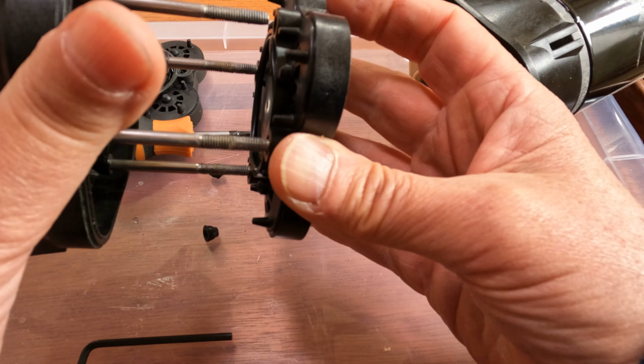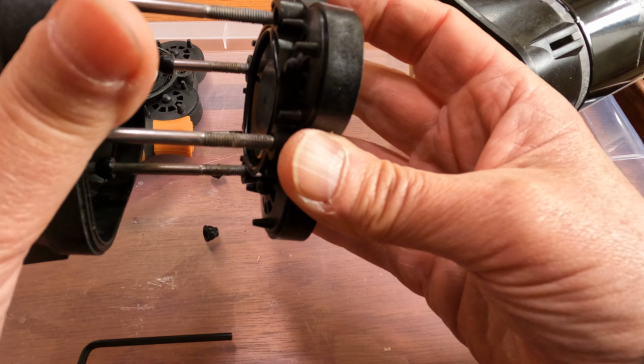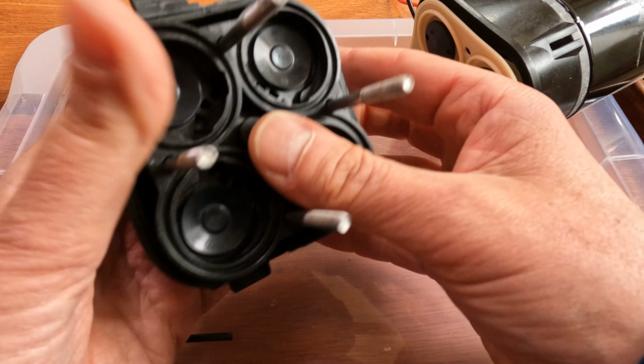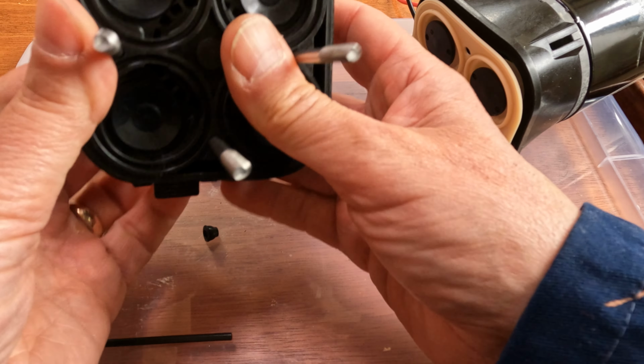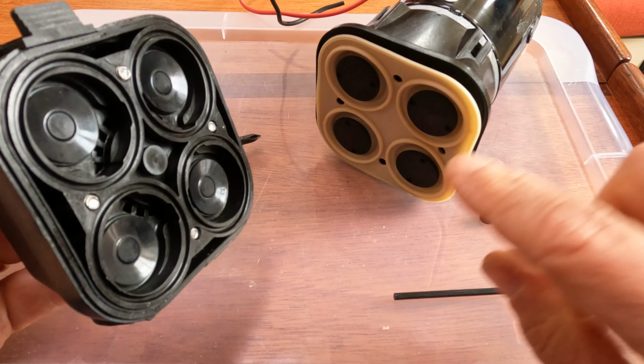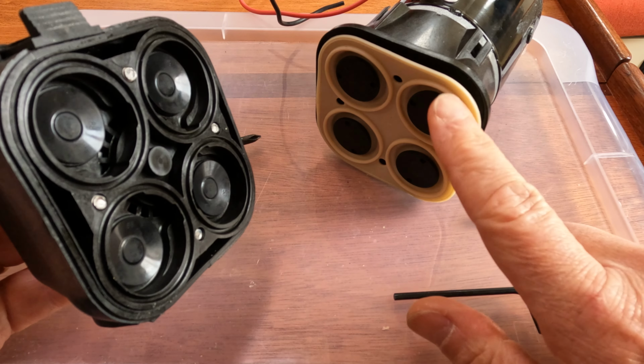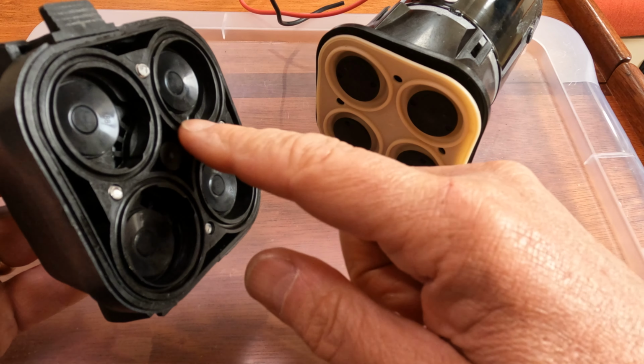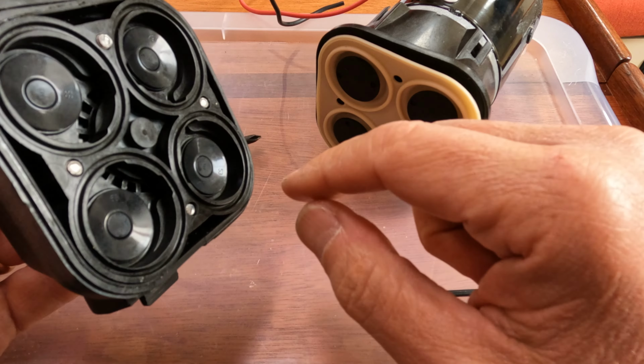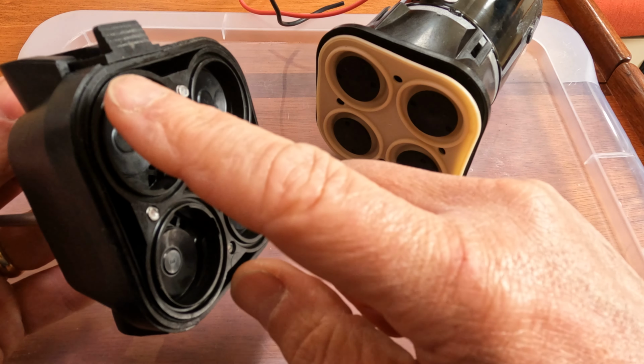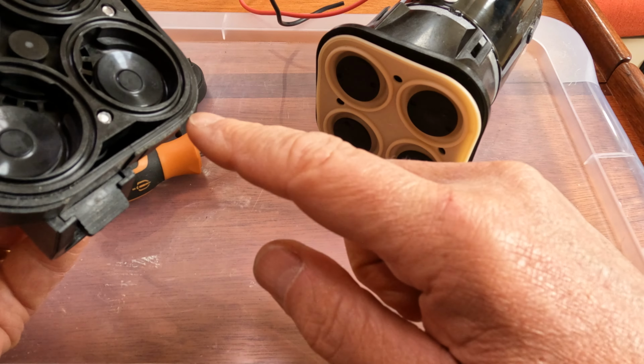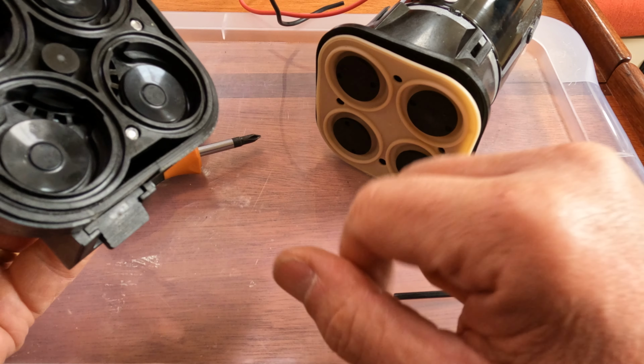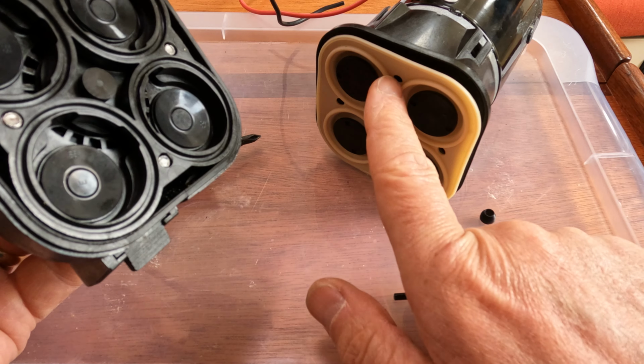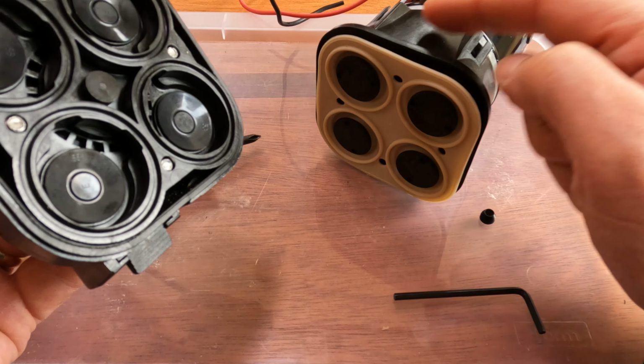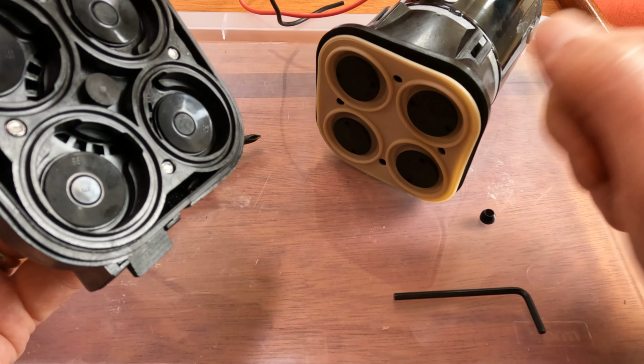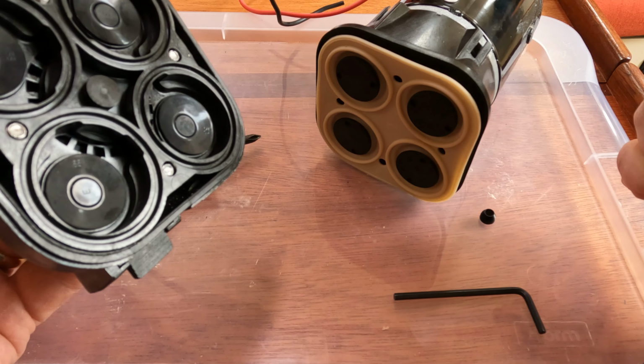So these bolts come through like that, and the whole thing - on this diaphragm there are grooves that match recesses in the pump head here, so when assembling I've just got to make sure that all of these match up nicely, and then the bolts just screw through into the lower half of the pump and clamp it all together to give us a watertight seal.